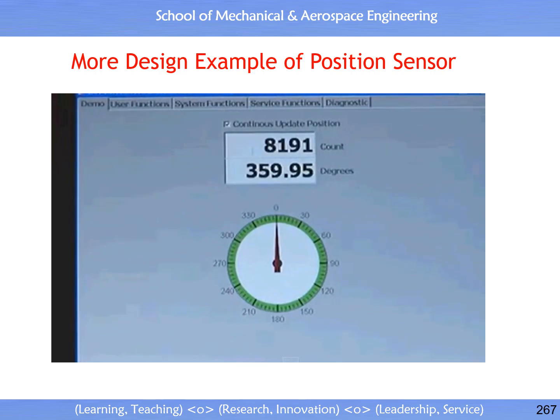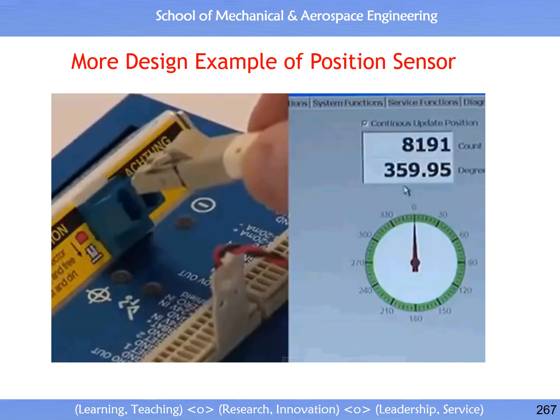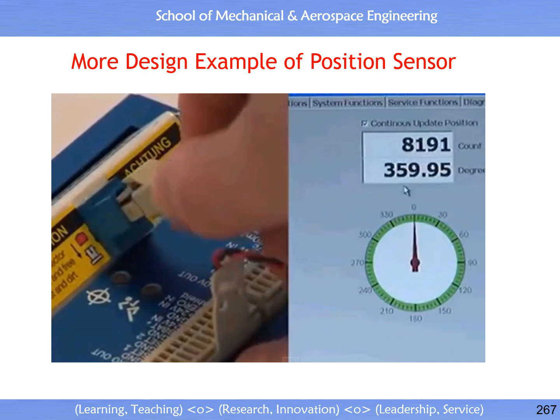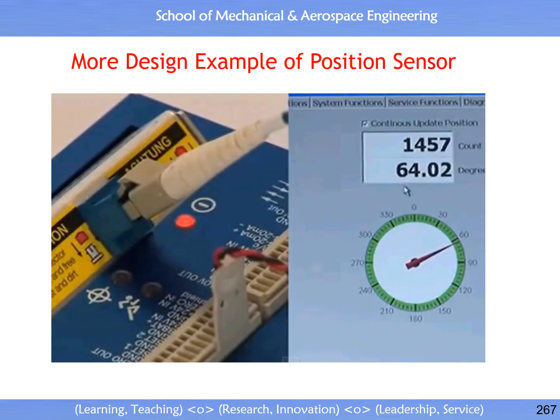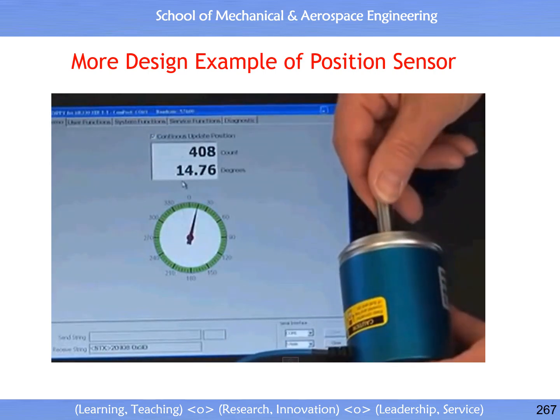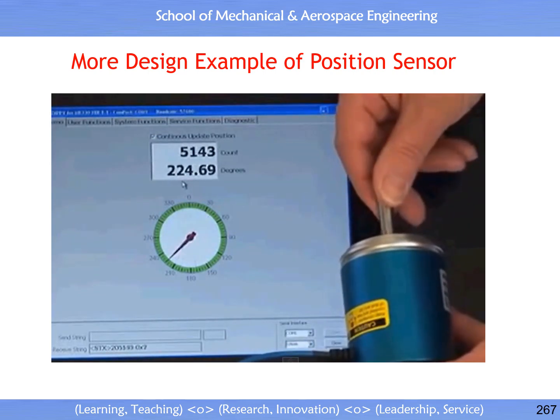For now, we leave the fiber optic cable unplugged until the readout software is running. While the sensor is disconnected, the maximum readout of 8,191 will appear. Now, we reconnect the optical fiber and the readout will return to the 1,457 position. The sensor will always know its exact position, whether the shaft is stationary or rotating.